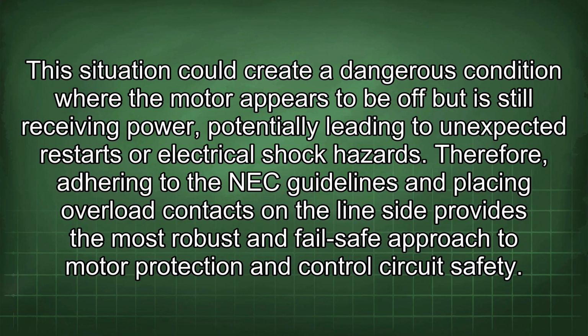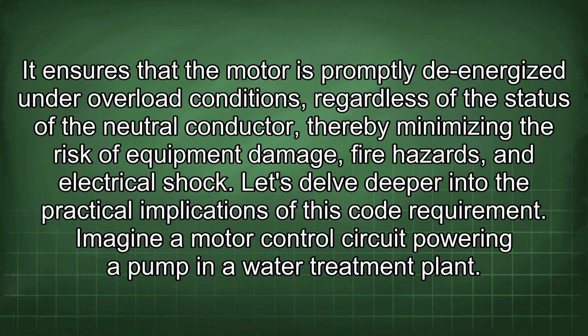Therefore, adhering to the NEC guidelines and placing overload contacts on the line side provides the most robust and fail-safe approach to motor protection and control circuit safety. It ensures that the motor is promptly de-energized under overload conditions, regardless of the status of the neutral conductor, thereby minimizing the risk of equipment damage, fire hazards, and electrical shock. Let's delve deeper into the practical implications of this code requirement. Imagine a motor control circuit powering a pump in a water treatment plant.